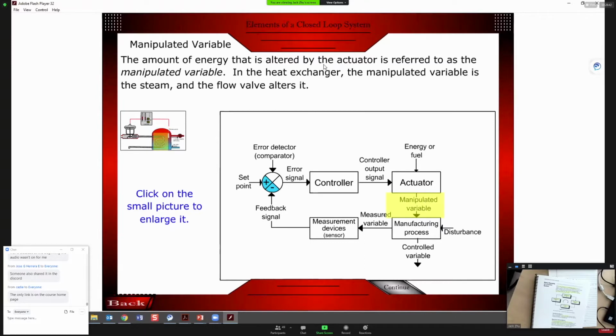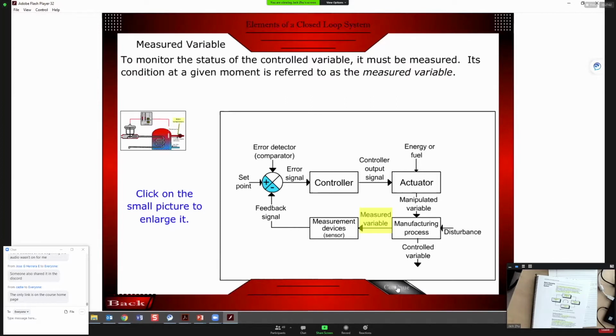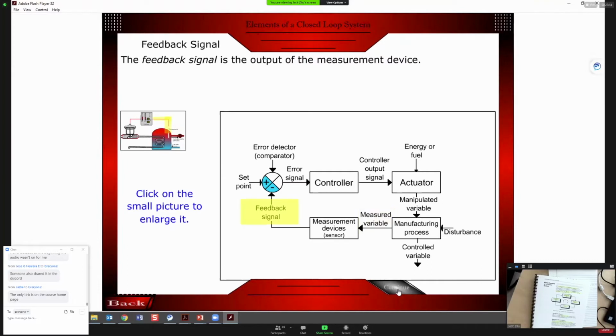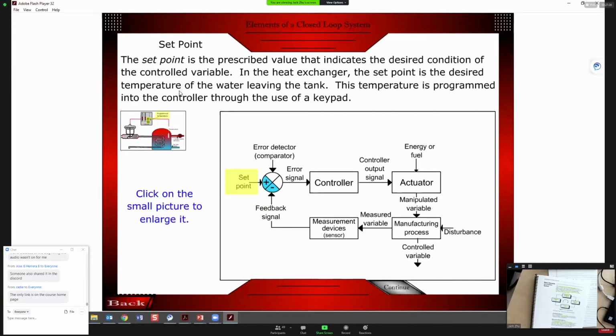The manipulated variable is the variable that's altered by the actuator. In the heat exchanger, the manipulated variable is the steam. So the valve will control how much steam can flow through the heat exchanger. The measured variable is the monitor of the controlled variable. So in here it is the temperature we try to measure. The feedback signal is the output of the measurement device. The set point is the prescribed value indicating the desired condition of the controlled variable. In here, the set point is the desired temperature of the water leaving the tank.